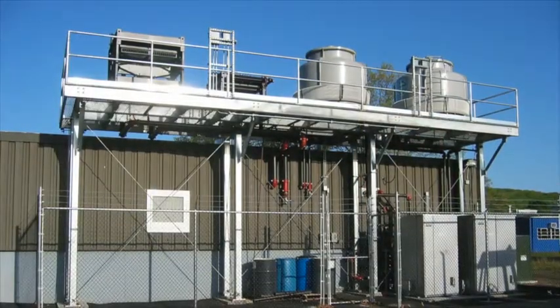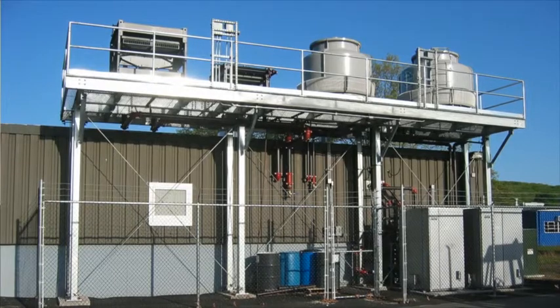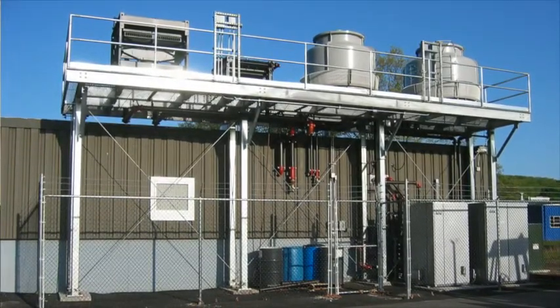That fuel is free because it's the waste heat coming off the generator. We take that waste heat and convert it to either chill water or hot water in the wintertime. So all year long that generator is running and supplying either heat or cooling for the building.